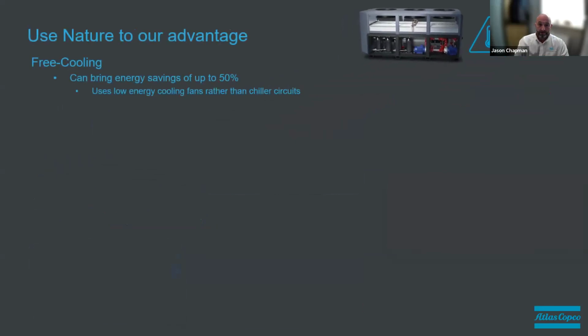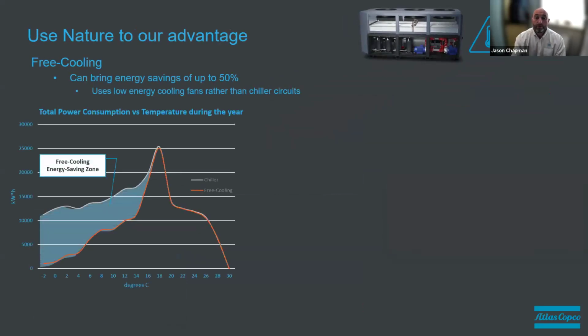So using free cooling to our advantage, what is the free cooling zone? As we said, it can reduce energy consumption by up to 50%. So how does this actually look? If we look at the graph there, the free cooling energy zone on the left-hand side is what's shaded in blue. As the free cooling runs, the white line above the blue is where the normal chiller would be running. The orange line that you can see is the free cooling zone. As you can see, it reduces the power consumption in kilowatt hours quite significantly. And this is the zone we're trying to take advantage of, especially in this country.